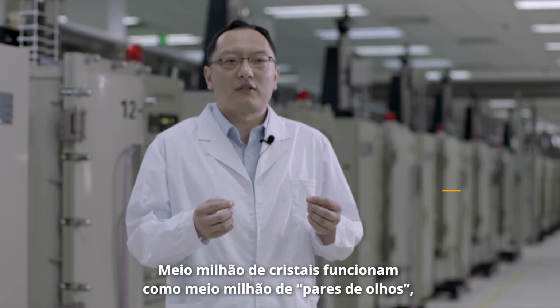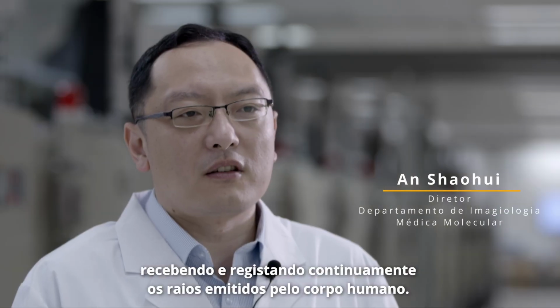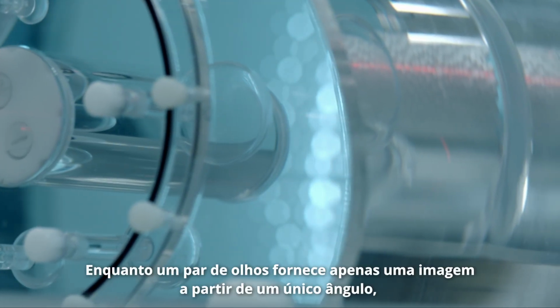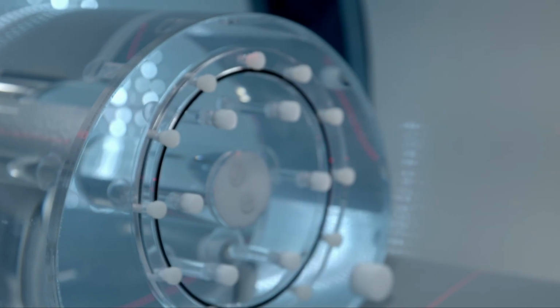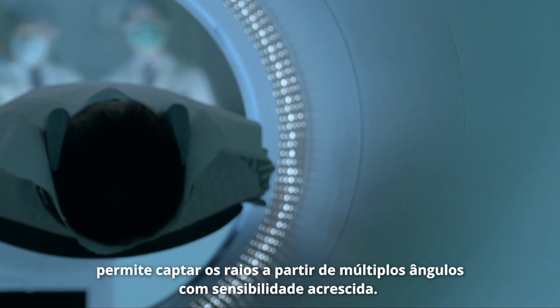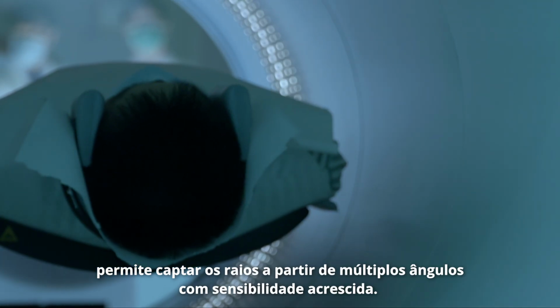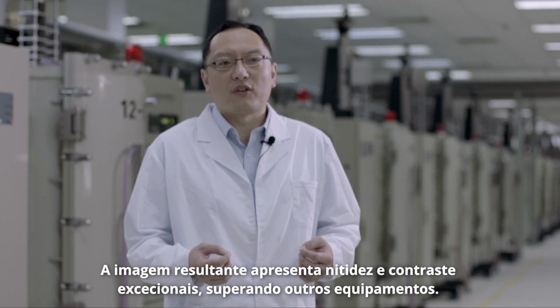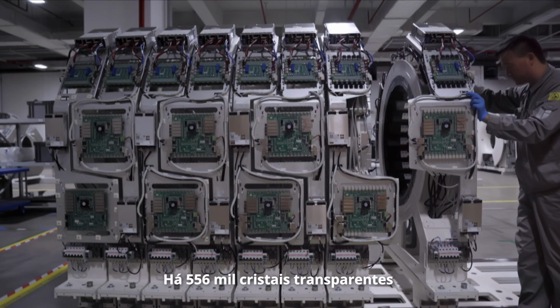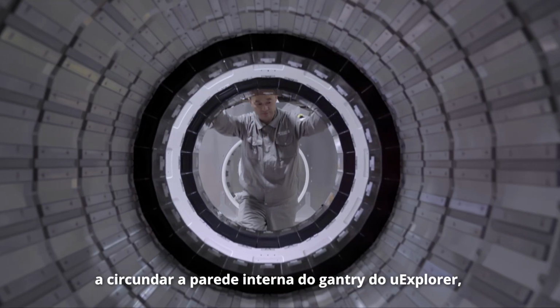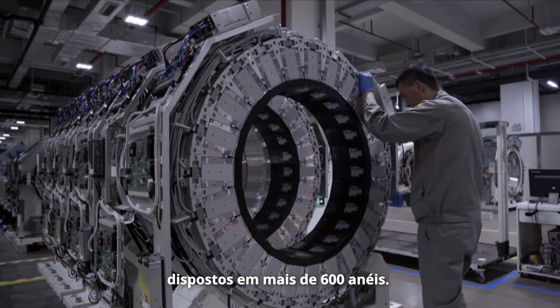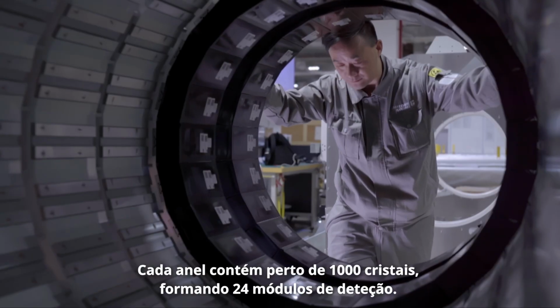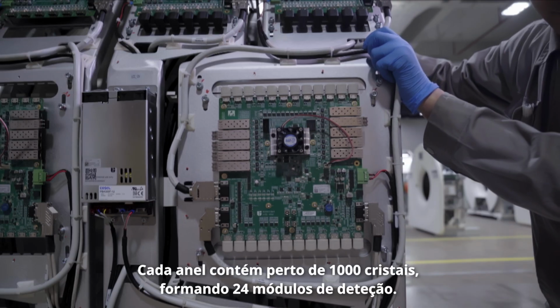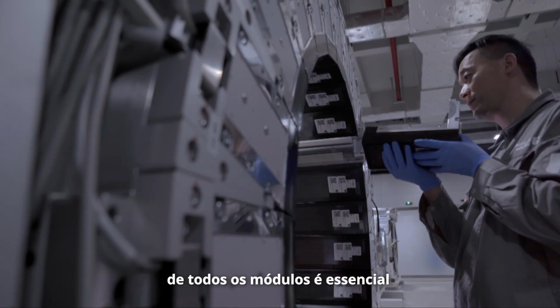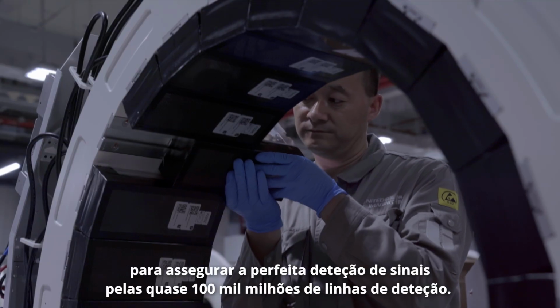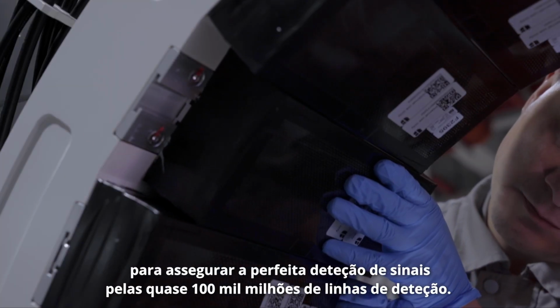There are 556,000 transparent crystals encircling the inner wall of the uExplorer's gantry, arranged in more than 600 loops. Each loop consists of close to 1,000 crystals, creating 24 detection modules. The precise and meticulous assembly of all the modules is essential to ensure the perfect detection of signals by the nearly 100 billion detection lines.